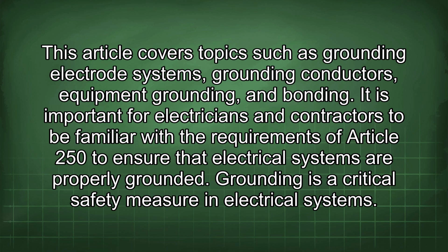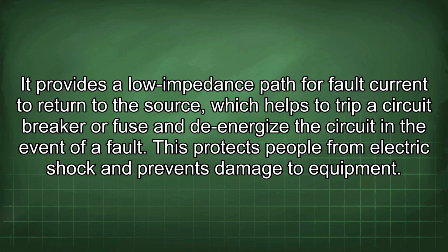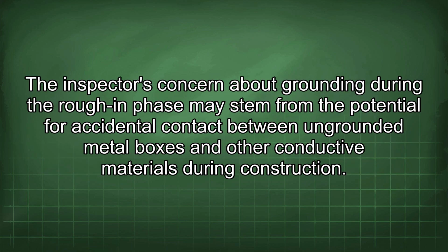Grounding is a critical safety measure in electrical systems. It provides a low impedance path for fault current to return to the source, which helps to trip a circuit breaker or fuse and de-energize the circuit in the event of a fault. This protects people from electric shock and prevents damage to equipment. The inspector's concern about grounding during the rough-in phase may stem from the potential for accidental contact between metal boxes and other conductive materials during construction.